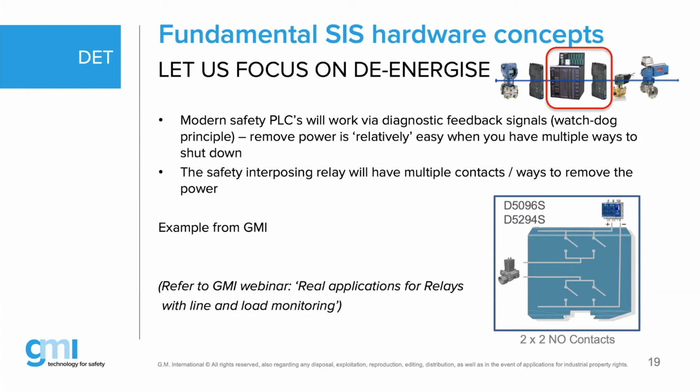And they could actually not remove the power on a digital output module. And in a panic, they actually had to remove the power on the complete module. So it all depends what brand you are using, what systems you are using, but the more modern systems can dedicate, isolate, channel per channel, the power going to the field.